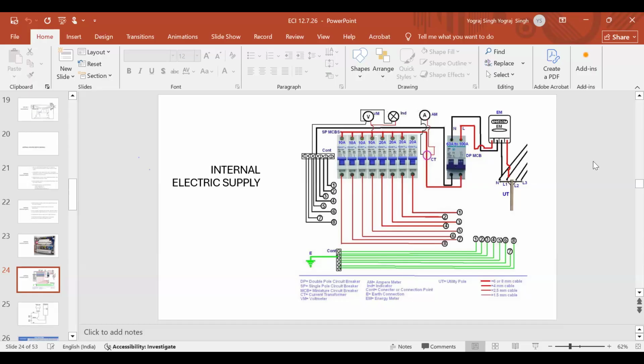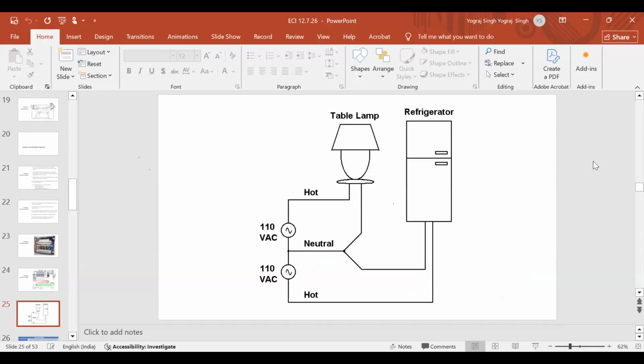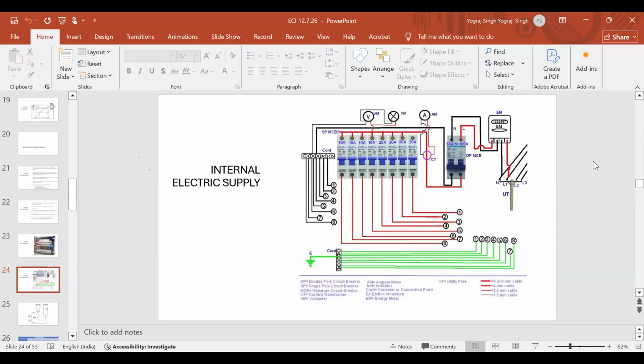What happens when the building is being constructed? The electrician is doing the wiring. Especially in neutral, the electrician has a tendency, suppose he reaches one end of the room and the next circuit is somewhere close by, to connect that neutral from this room to that room, which should not be done, because an independent system should come from my distribution board. The same thing applies to earthing. Earthing is very important, because if earthing is not independent, it will create havoc.